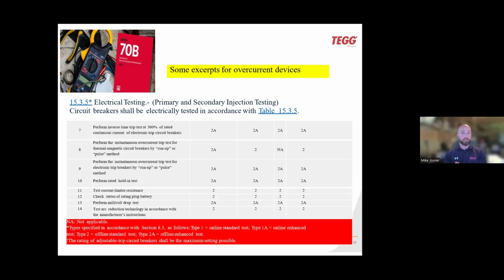You normally see that mostly for acceptance tests before this equipment was installed and sent off to your locations. The secondary injection testing tests the instantaneous trip, the trip settings, the relays, everything that's internal, for the CTs of the actual breaker itself. And then we can jump on to the next one. Are there any questions on this one?